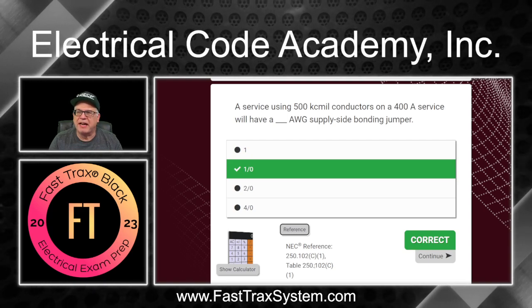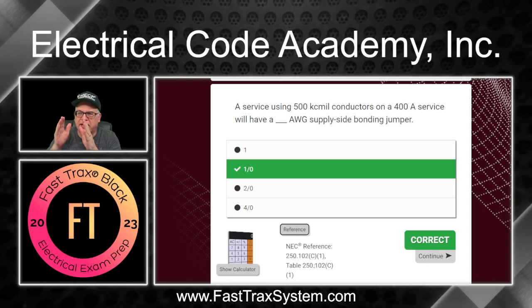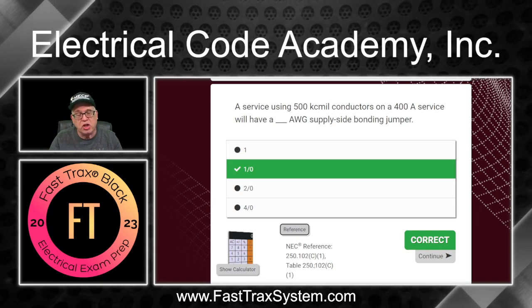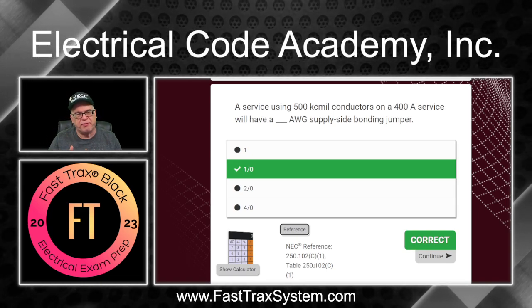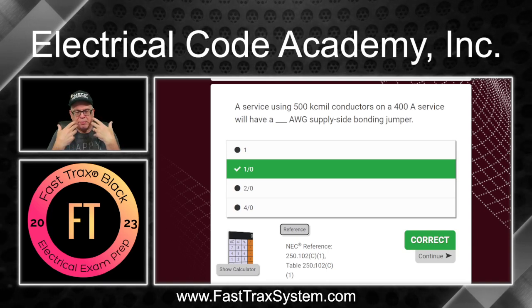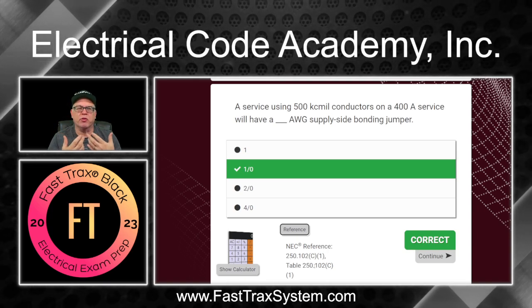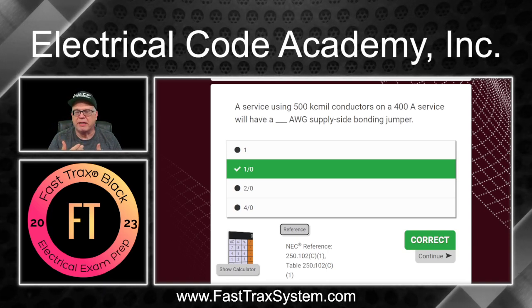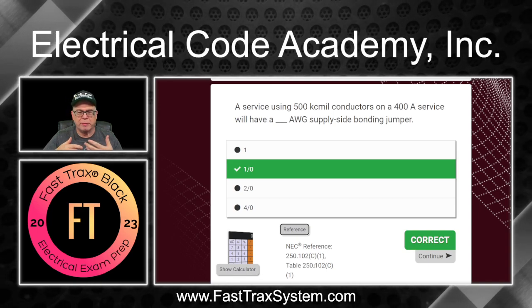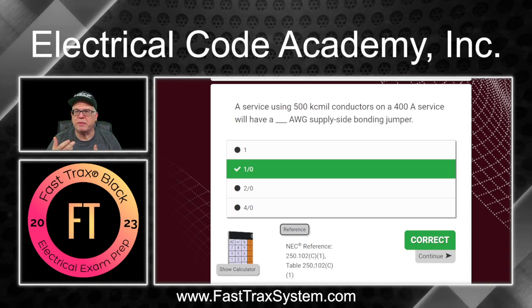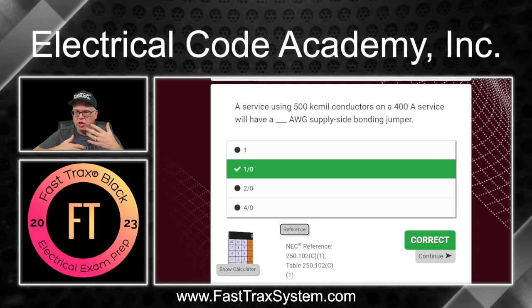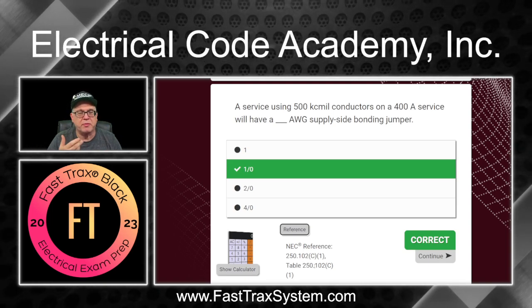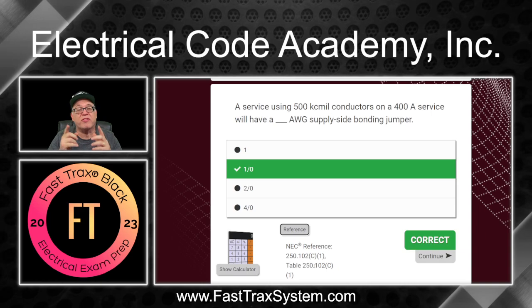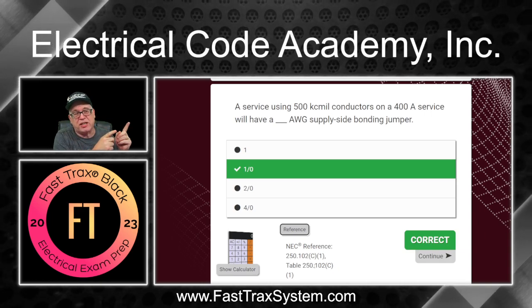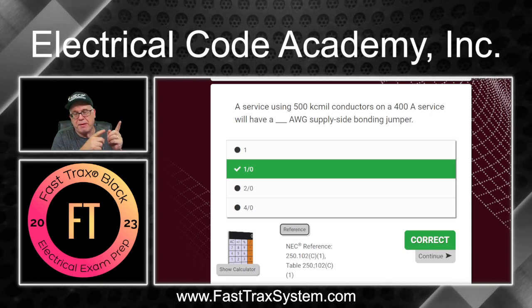You're not going to find supply side bonding jumper. You're going to find jumpers bonding. You go to service and it gives you multiple references. You should be able to look at that, and over time, you're going to know that 28's main bonding jumpers, okay? You're going to be looking at 66, and that's going to be grounding electrode conductors.